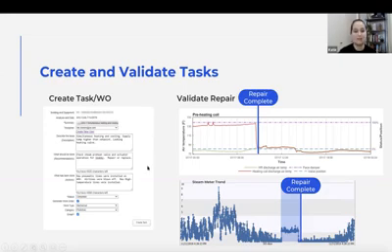In this particular issue, the pneumatic lines were blown off of the C2P valve. So new high temperature pneumatic lines were put in their place to hopefully prevent this from being a recurring problem. The pneumatic lines were sort of melting off of the valve. So you can see again, the repair is complete.